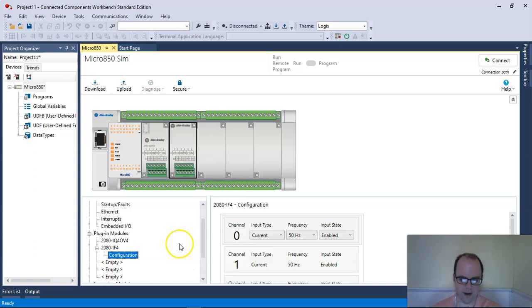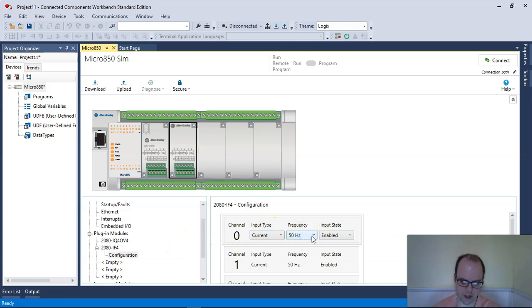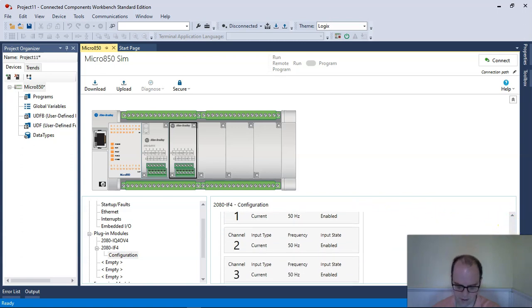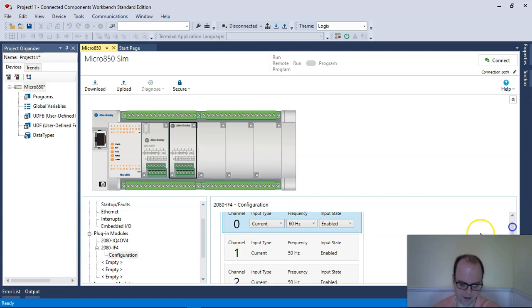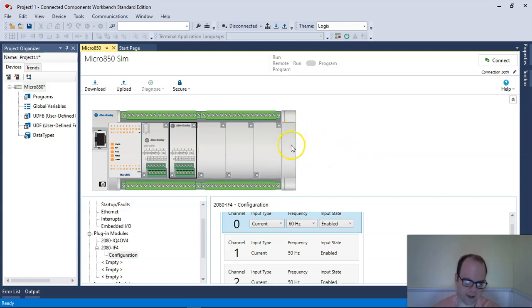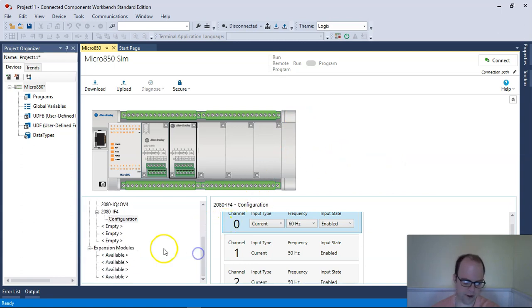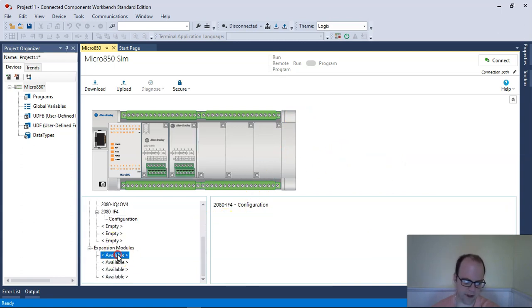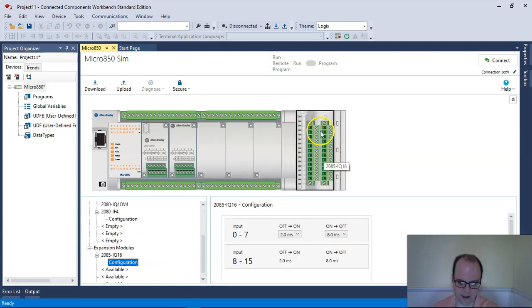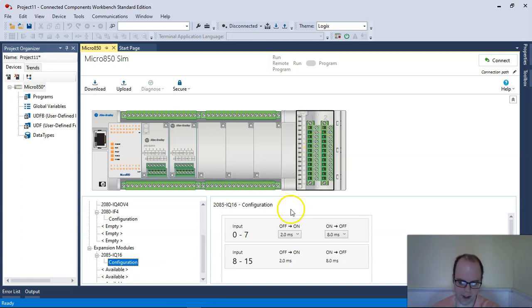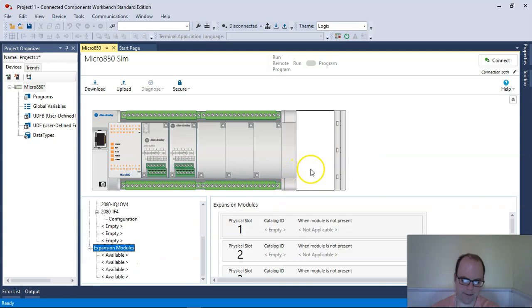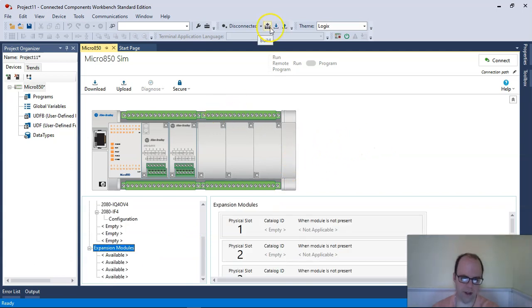I could also add an analog card. Remember, analog is a range. I could actually configure it based upon current for each channel. I can enable the input state. I could do it based upon current or voltage, depending on how I want to set things up. In theory, I could also have add-ons to this. There's expansion modules that you could also add, like digital expansion modules, a 16 input setup, and I could configure the on-off time.